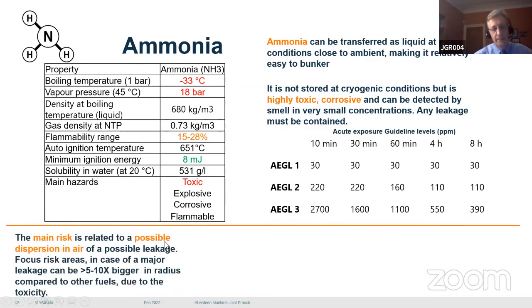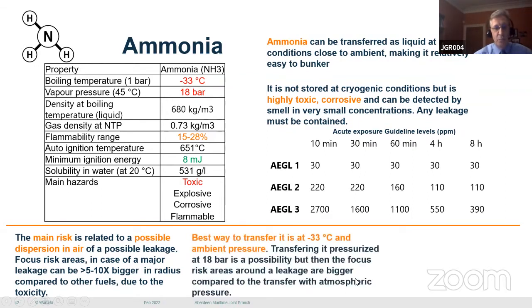The main risk would appear to be a possible dispersion in air of a leakage. The focus area in the case of a major leakage could be 5 to 10 times larger in radius compared to other fuels due to this toxicity. That's a serious problem. The best way to transfer it is at minus 33 degrees in ambient conditions. It can be transferred by pressurizing at 18 bar, maybe for smaller volumes, but then the focus of the design would be the risk areas around potential leakage, as those are greater compared to transfer at atmospheric pressure.